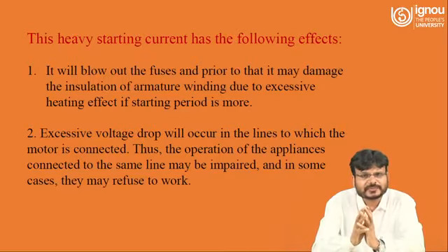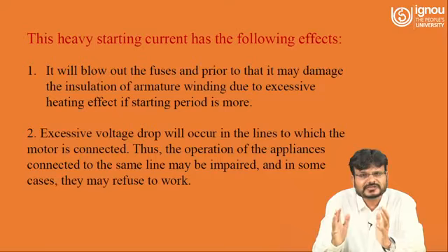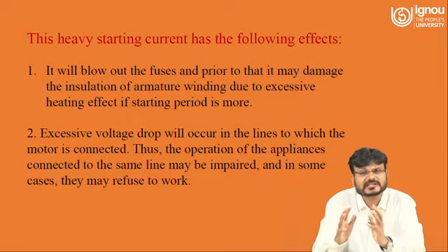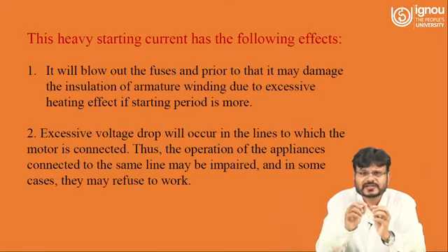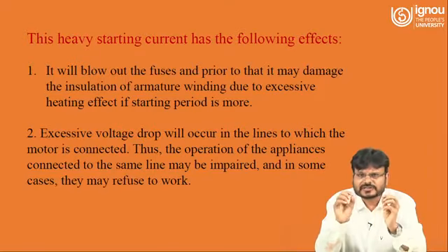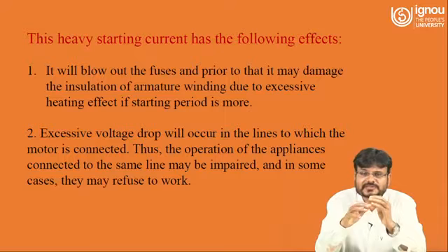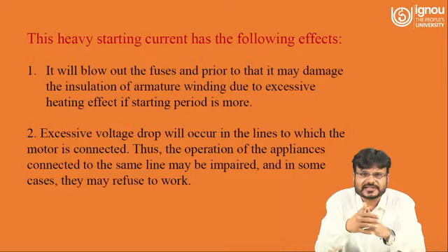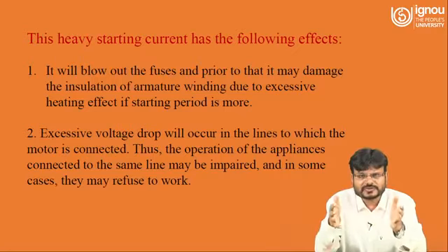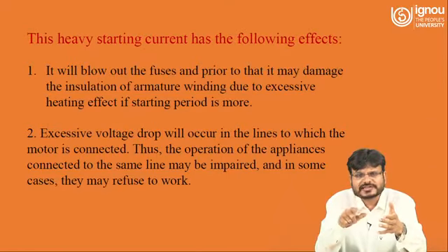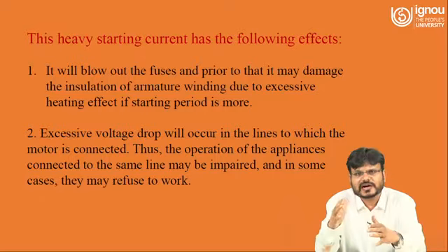In that case, what will happen? It will blow out the fuses, and prior to that it may damage the insulation of the armature winding due to excessive heating if the starting period is long, because the armature current is high. What is heat? Heat is H = I²R. That means if the current is very high, I²R will also be very high. Now suppose the period in which this heat is developed, t, is very long. So H is equal to I²Rt.